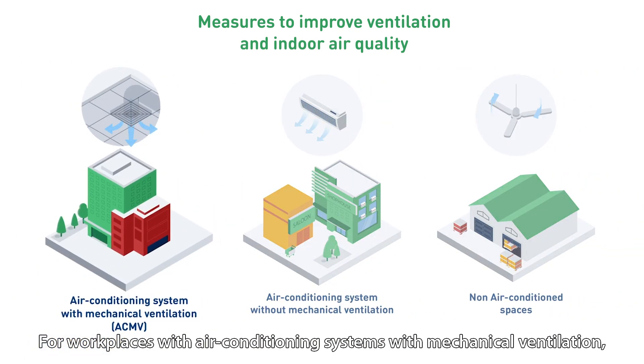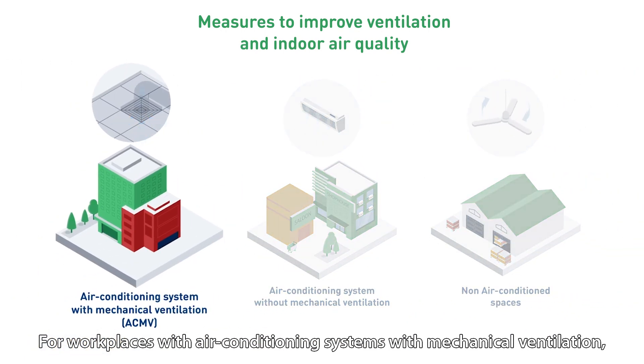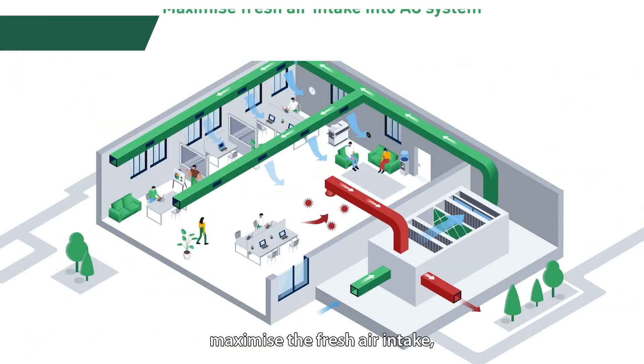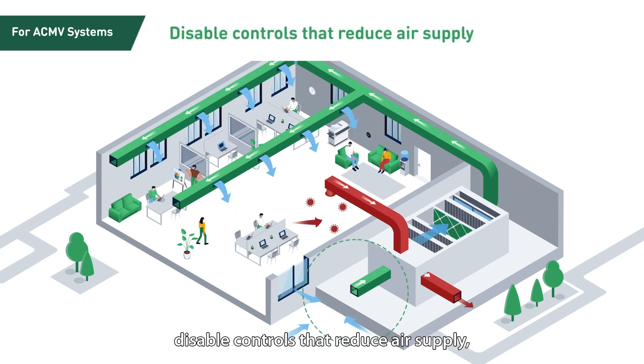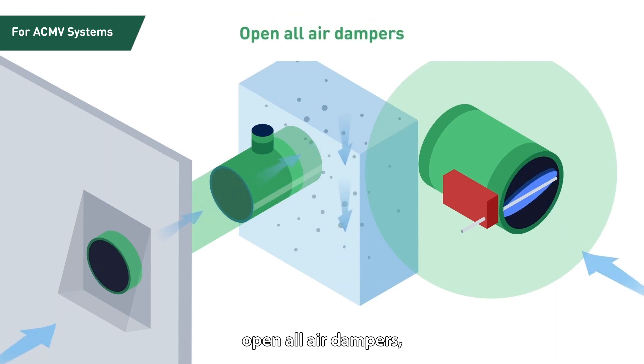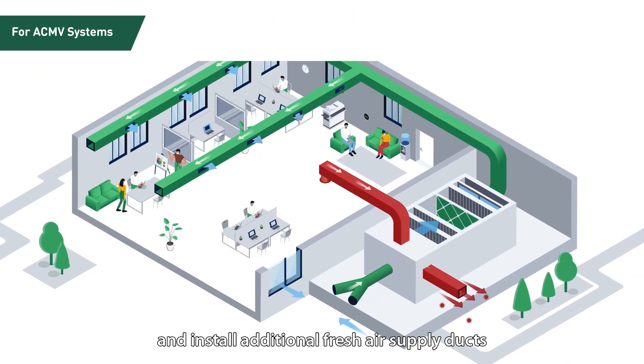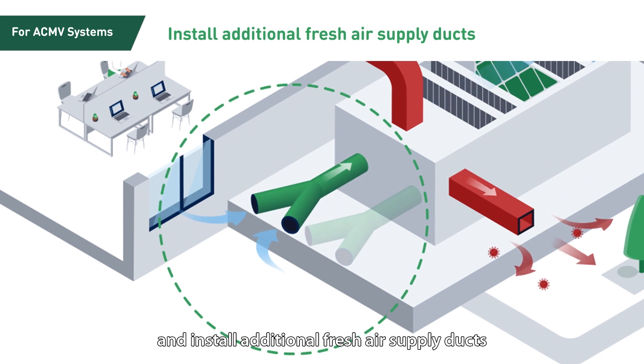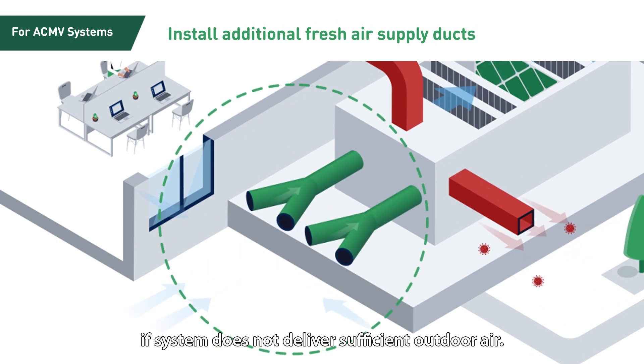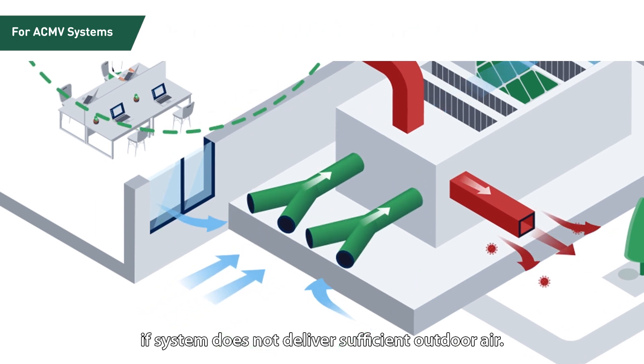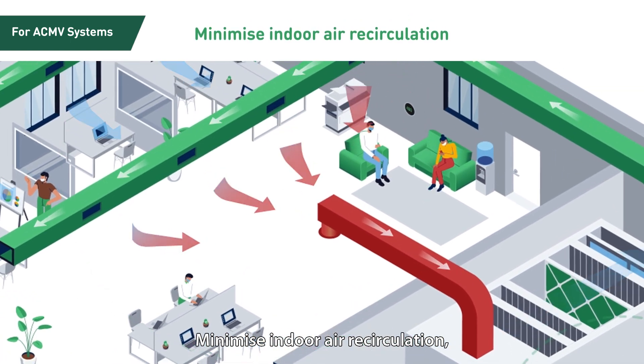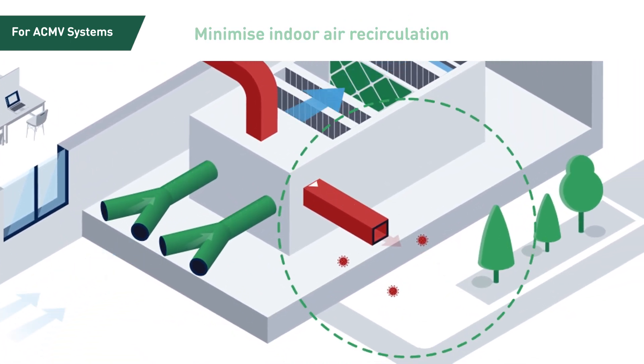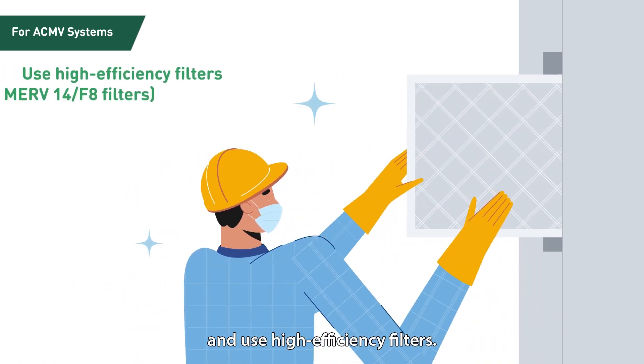For workplaces with air conditioning systems with mechanical ventilation, maximise the fresh air intake. Disable controls that reduce air supply. Open all air dampers and install additional fresh air supply ducts if the system does not deliver sufficient outdoor air. Minimise indoor air recirculation and use high efficiency filters.